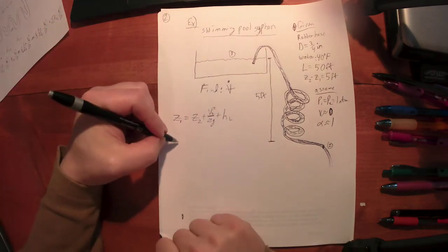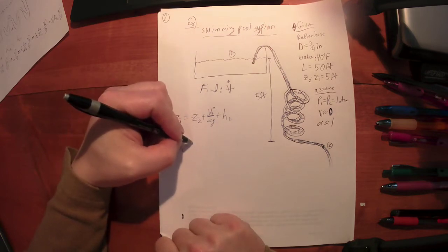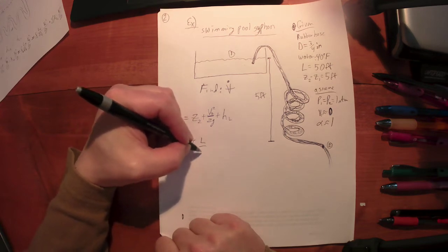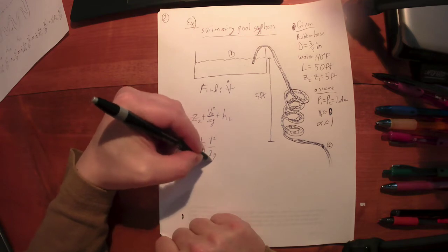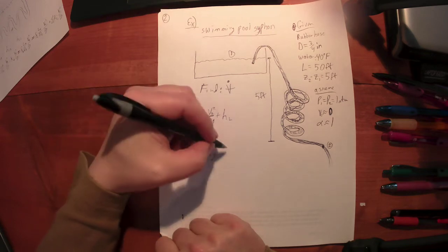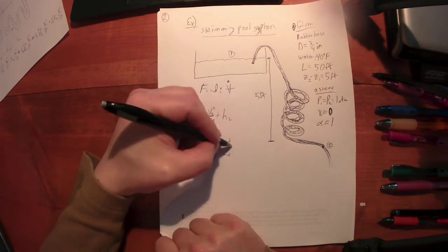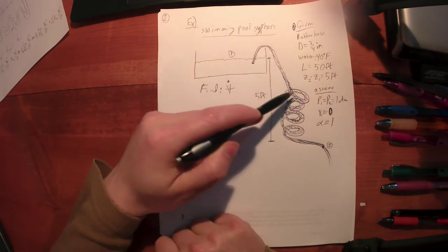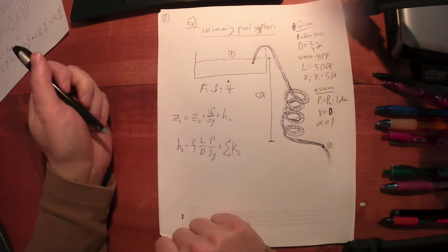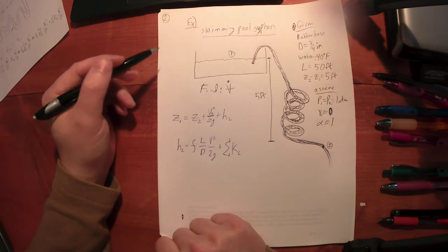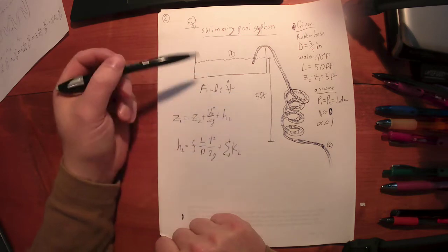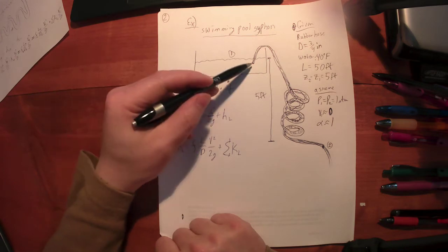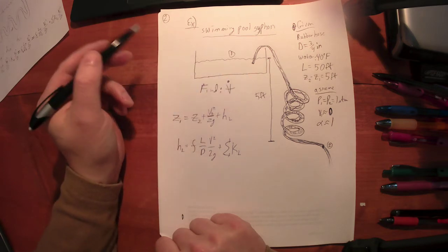Okay, so how do we find this head loss? Well, I'm going to have both major and minor losses. I've got a 50-foot section of hose here, FL over D, V squared over 2G. And I'm going to have a minor loss. I've got a bunch of bends, so let's see if we can approximate a minor loss for each one of these bends. I've got 9, I guess. I've got 4 coils, so there's 2 bends on each coil. So 9 bends. And I've got a pipe inlet there we probably want to account for.